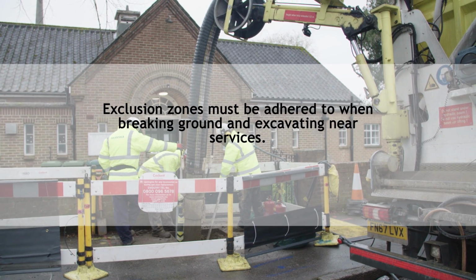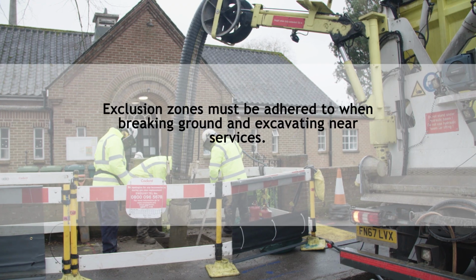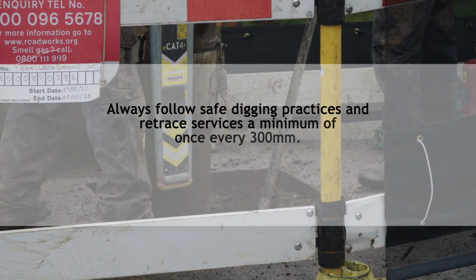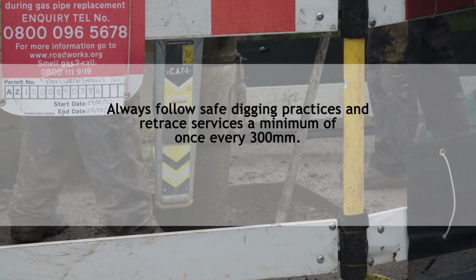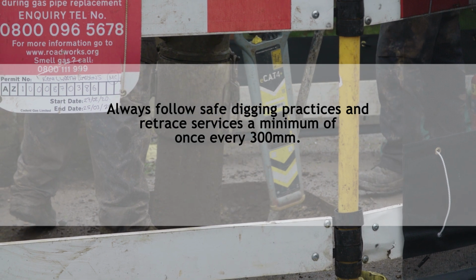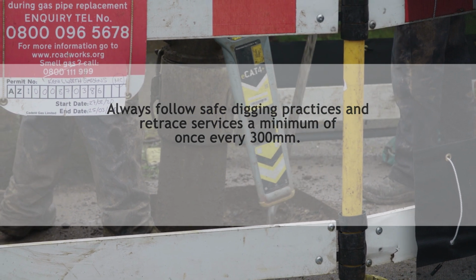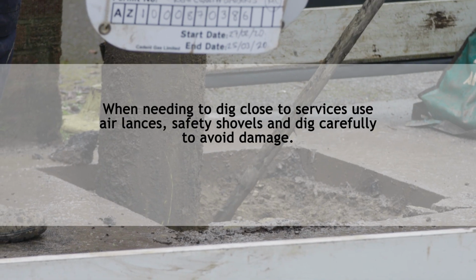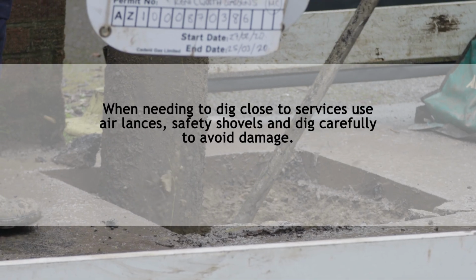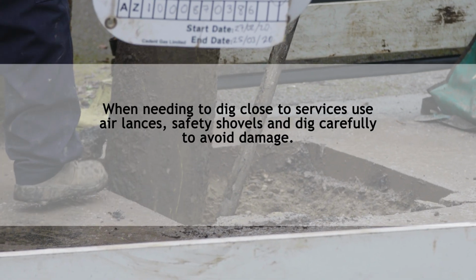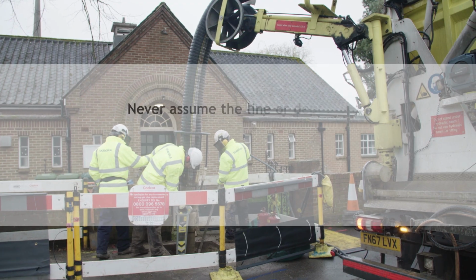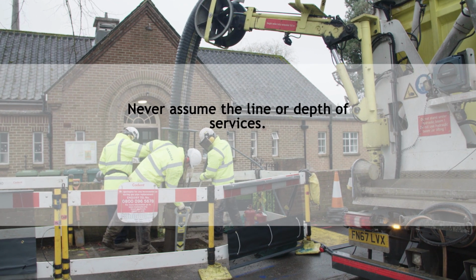Exclusion zones must be adhered to when breaking ground and excavating near services. Always follow safe digging practices and retrace services a minimum of once every 300 mm. When needing to dig close to services, use air lances, safety shovels, and dig carefully to avoid damage. Never assume the line or depth of services.